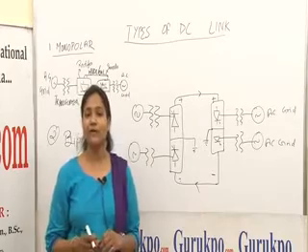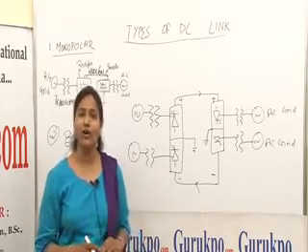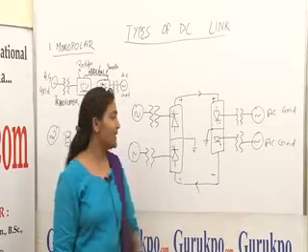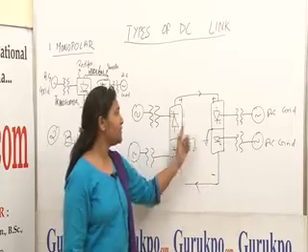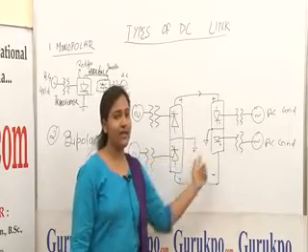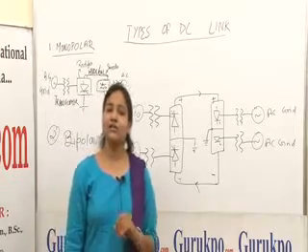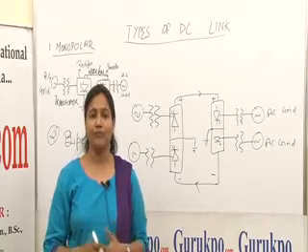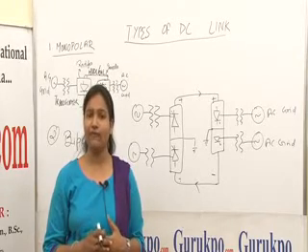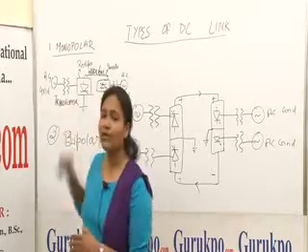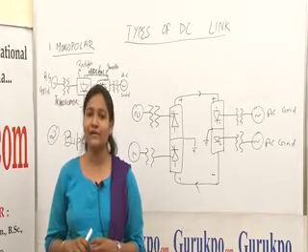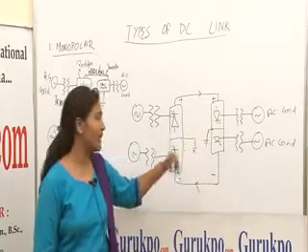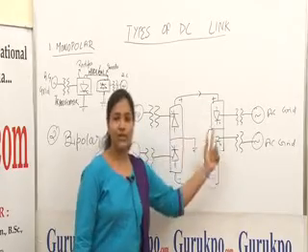In the bipolar link, there is a benefit that if due to some maintenance or fault, one of the conductor systems is under non-working conditions, then the system can be used as a monopolar link using the ground as a return path. Hence the stability of this system is very high as the power capacity can be reduced to half. But in the monopolar system, if there is some fault, the whole system is out of working. In the bipolar system, half of the load capacity can still be carried out by converting it into a monopolar system.